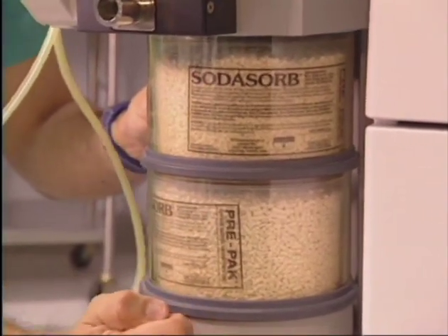In Grand Rounds this year, we had a discussion on pouring water into the absorber, and at our institution, they said not to do that. If you had any concern about it, take off the lower canister, if not both, and replace it with fresh. Does the insert on the absorber say that you can pour water into it? I don't know. But I know you can. And I know that there's been at least one study that suggests that you will rehydrate the absorbent simply by pouring water into it.